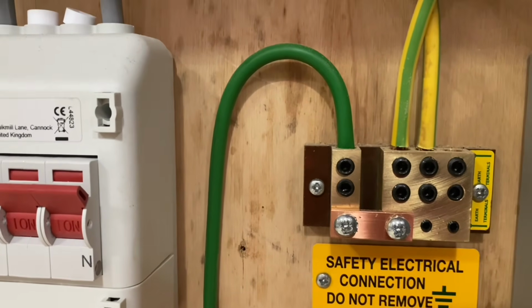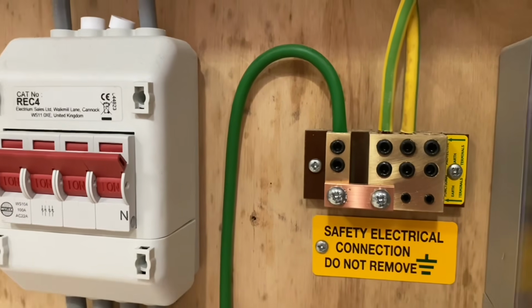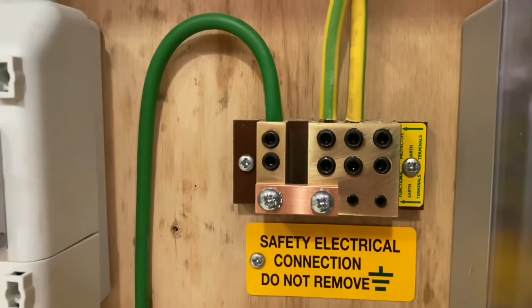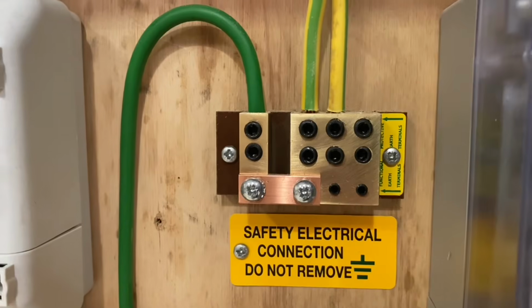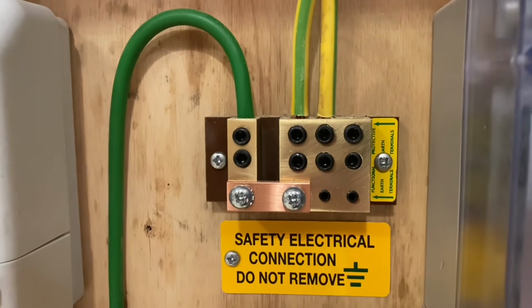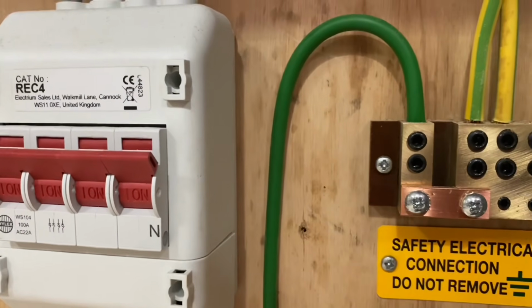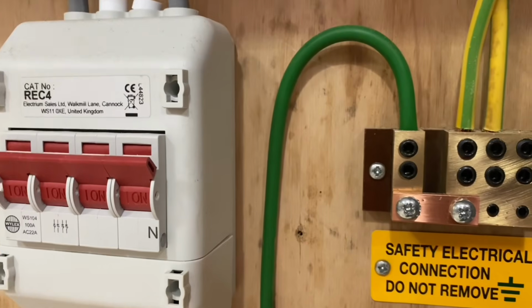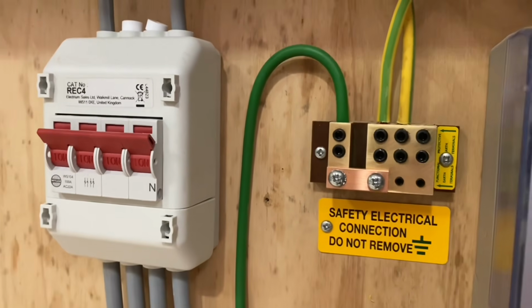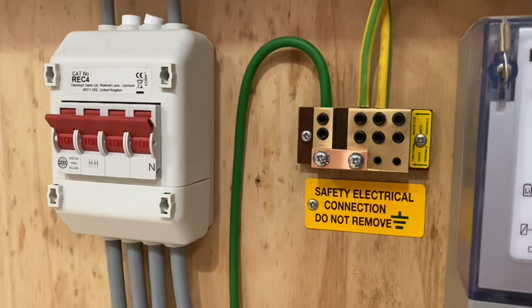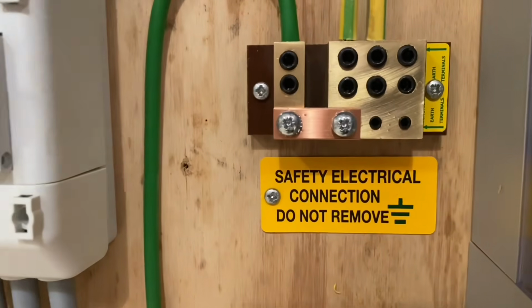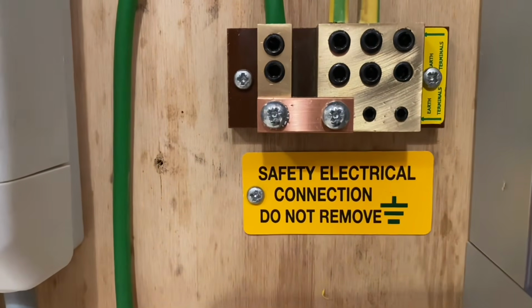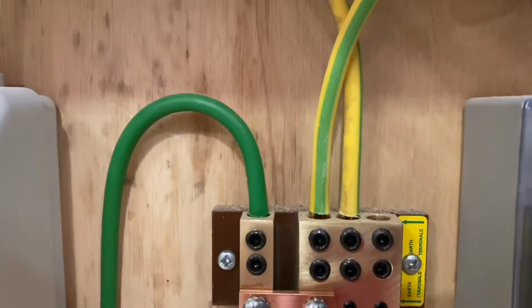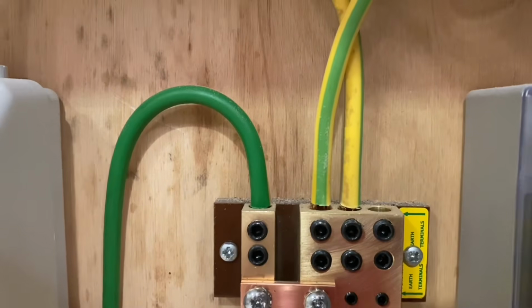reading. There is a link on this one, special MET, where you could remove the link, because on the right-hand side you have a conductor going to the bonded steel framework of the building and the other one goes into the distribution board. I'm going to show you at the very end of this presentation how Matt carried out his external earth fault loop impedance test where he didn't have an MET, but it's likely you will have an MET at AM2 or AM2S.